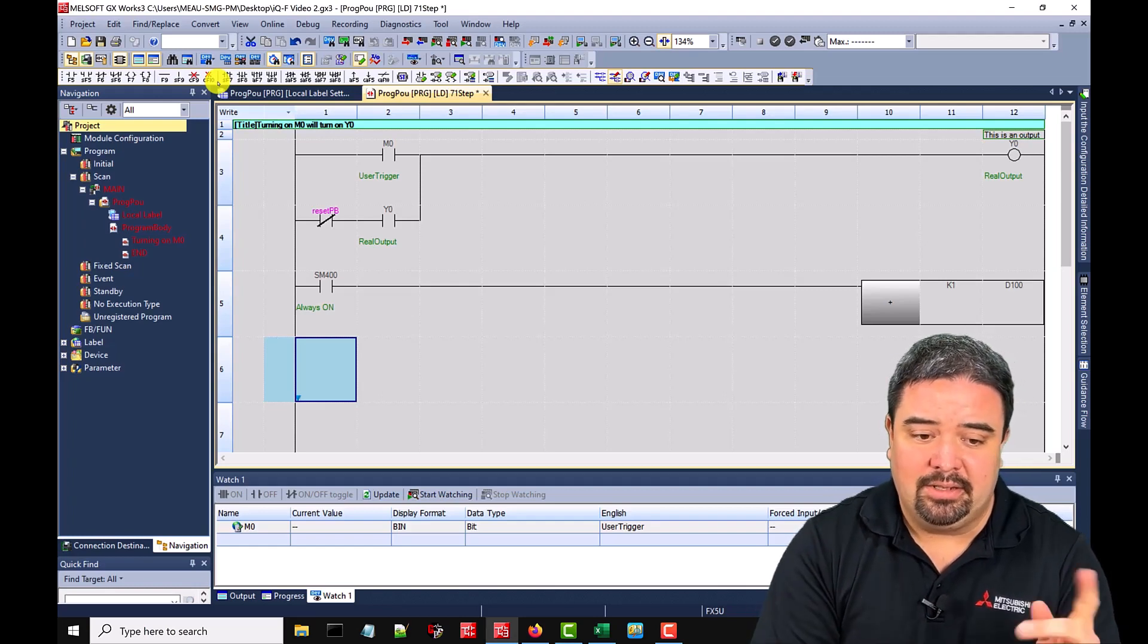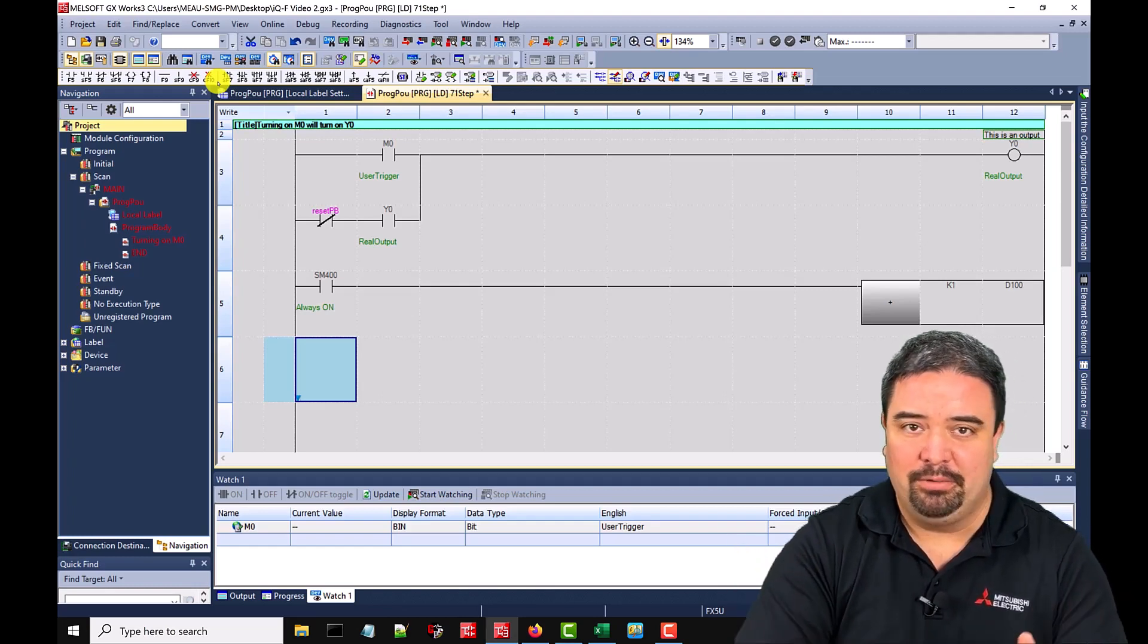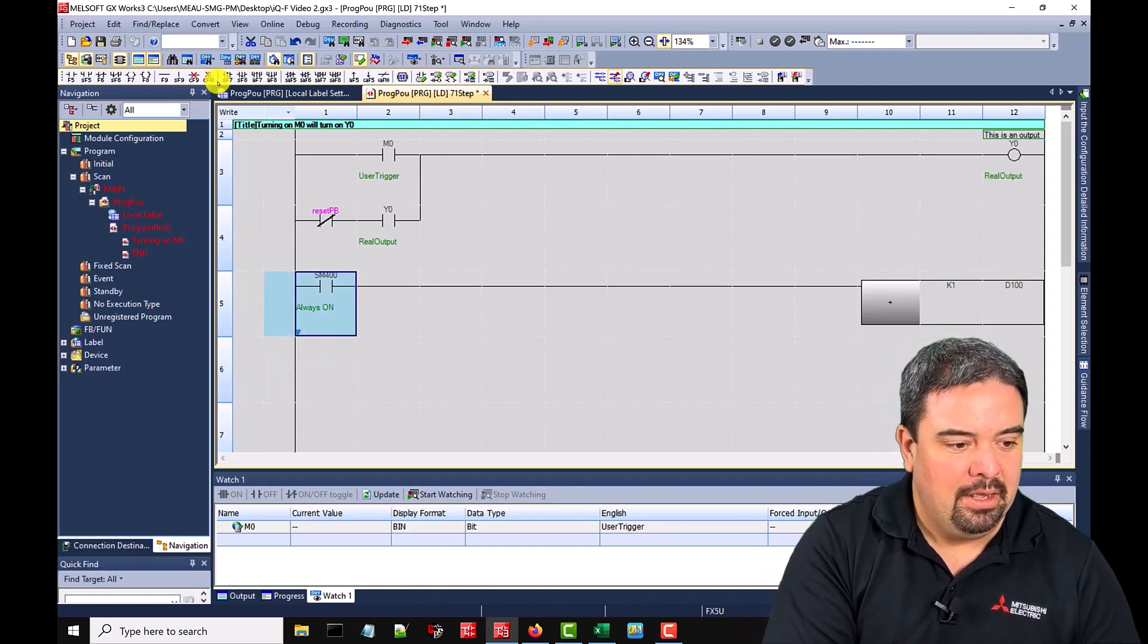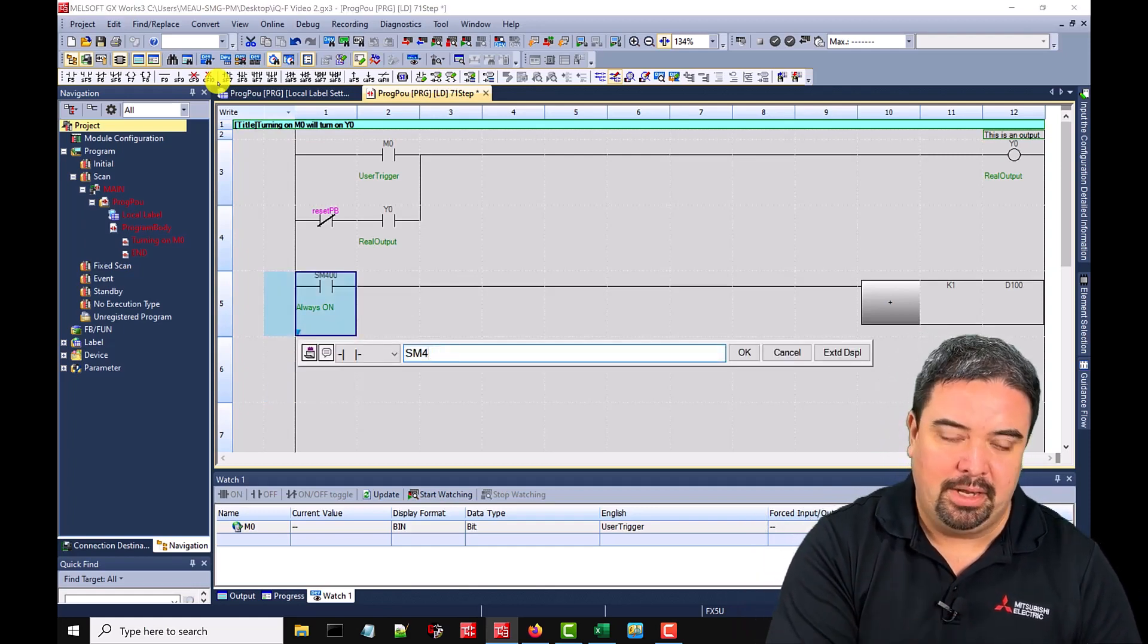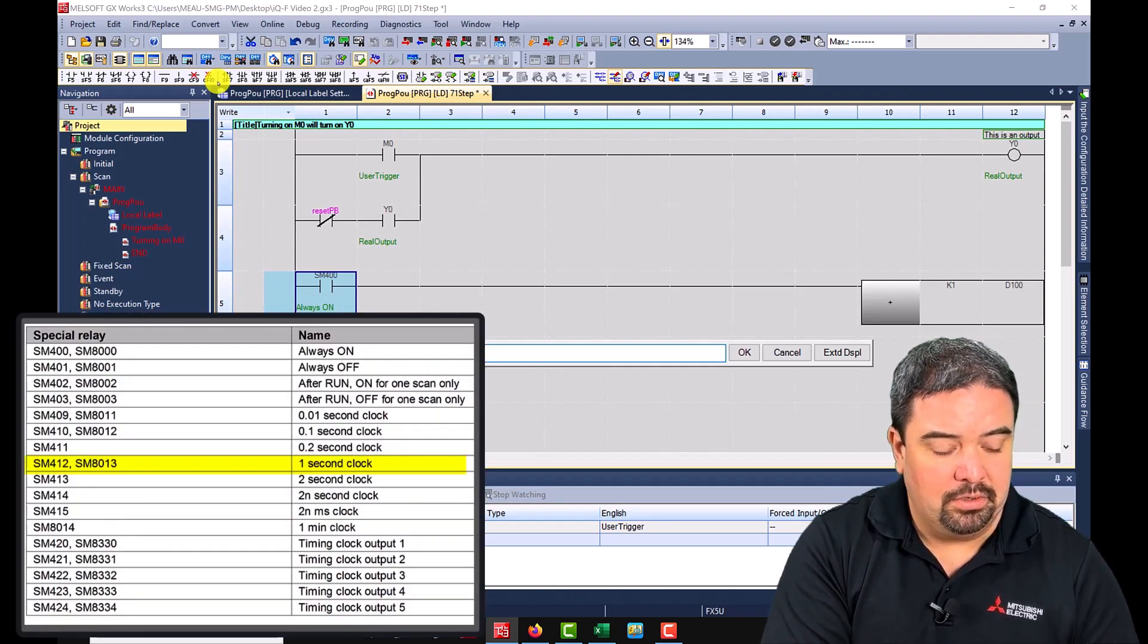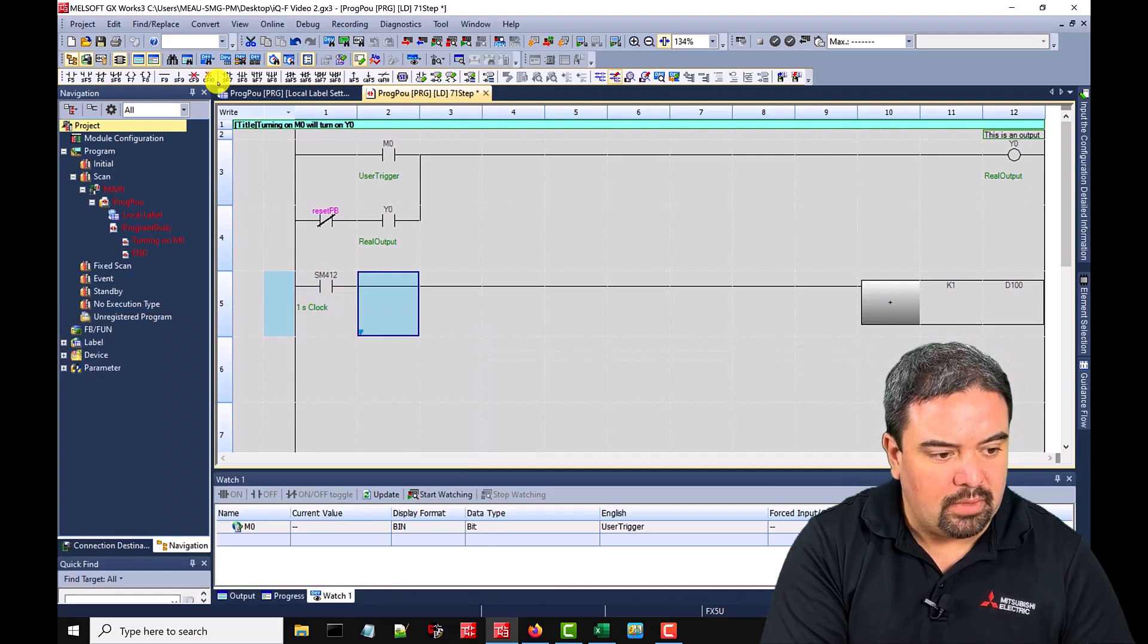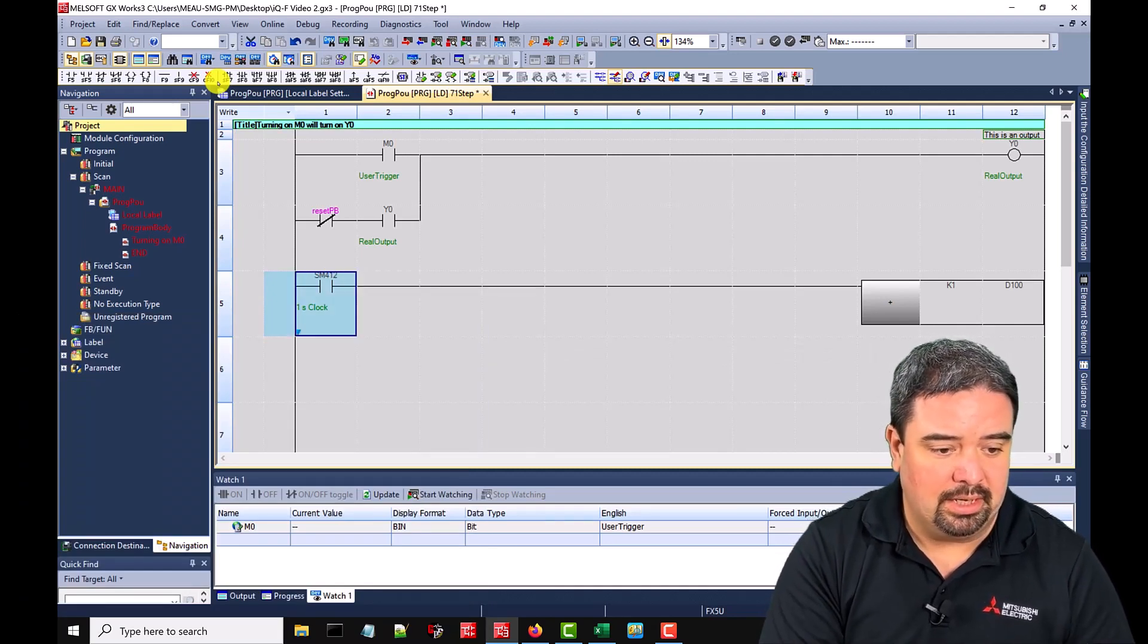Now, if I do that, every time the PLC scans, it's going to keep adding one until that buffer's full in the register and it'll start over at zero and it'll keep going. So I probably don't want that. So maybe I'll give this a pulse command and just see it incrementing that register. So SM412 will be a one second pulse. And you can see that it automatically told us in the comments, one second clock.